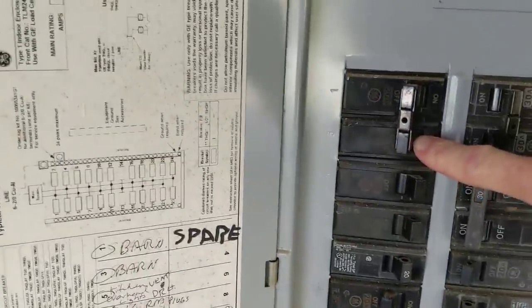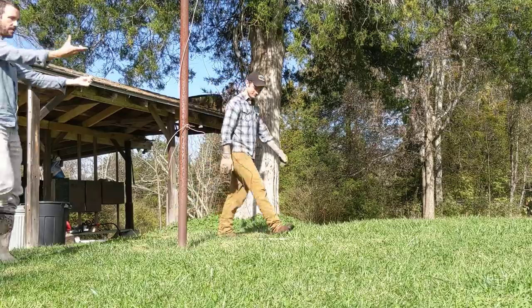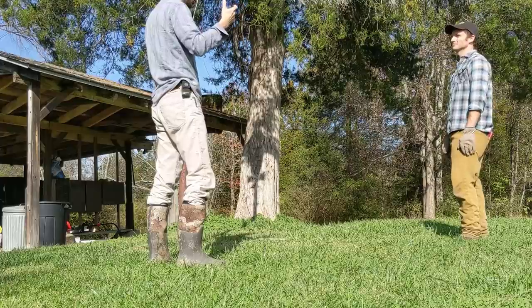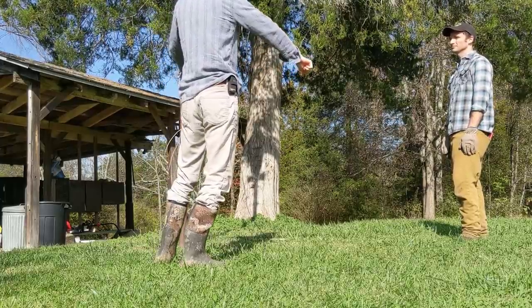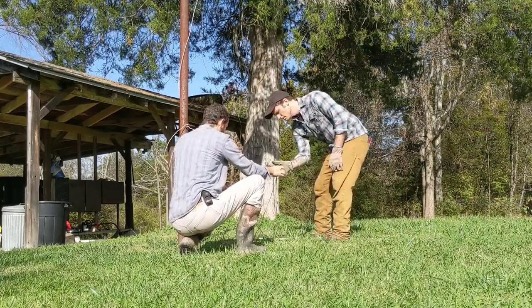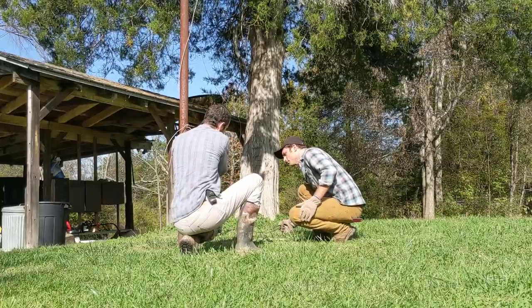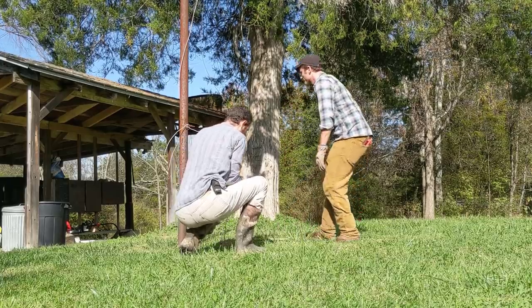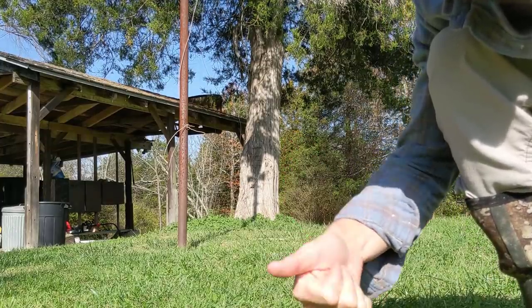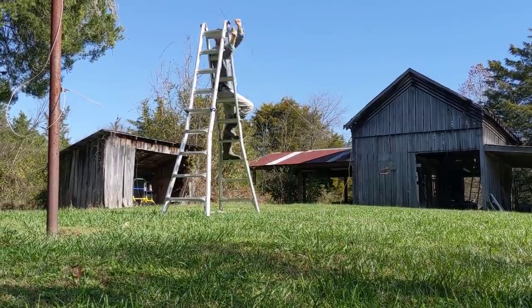Barn breakers one and three are off. As long as you're not holding one end with your hand here and the other end with your hand here - that completes the circuit and causes your muscles to spasm and you can't let go. Let's just verify that we're off again. All right, I'm touching the wires and I'm not seeing anything. We are golden to start connecting. We verify that it has power when the circuit breakers are on, and no power when they're off. Good to go.